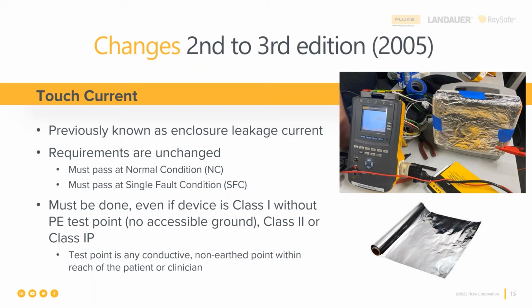And so by putting this aluminum foil on the outside, we have completed that capacitor. Current flow and conductors inside, the plastic is the insulator, and then the aluminum foil is the conductor on the outside. We clip our test lead to that, and voila, we make the correct measurement, and we are able to identify what is the worst case, that means the biggest leakage current available, whether it's power on, power off, normal or reverse polarity, or when we run the single fault conditions called open neutral or open ground. Okay, aluminum foil about a 10 centimeter square, 2 or 3 thicknesses, and wrap the edges together and then tape it down, just as you see in the picture here.